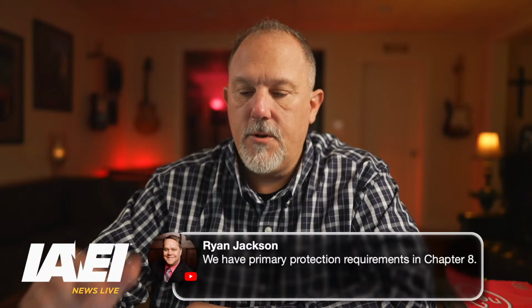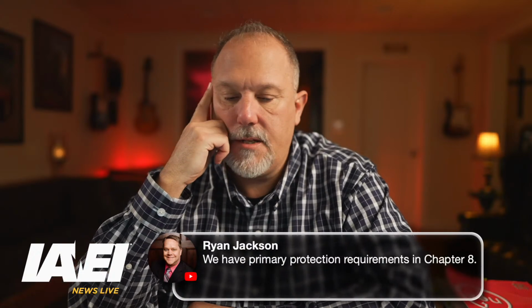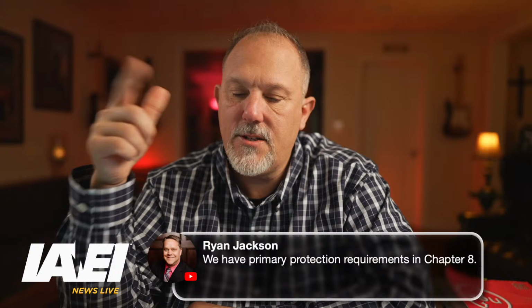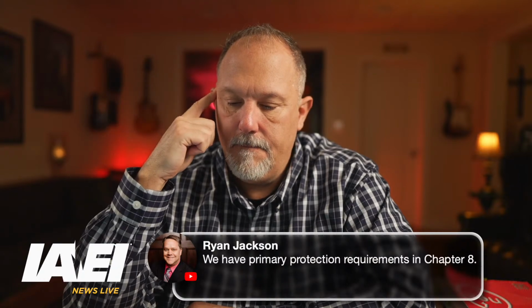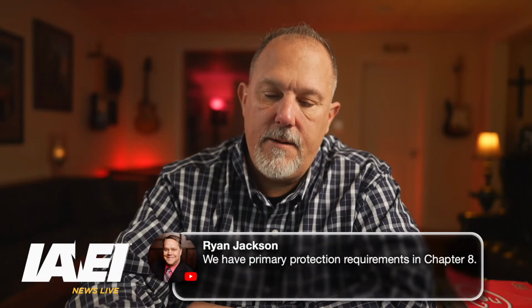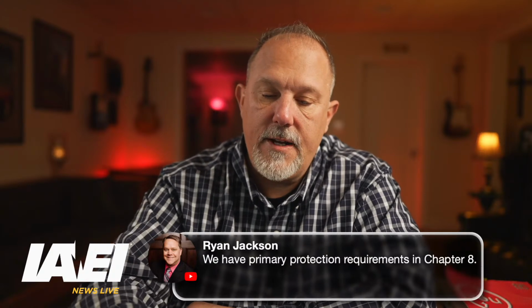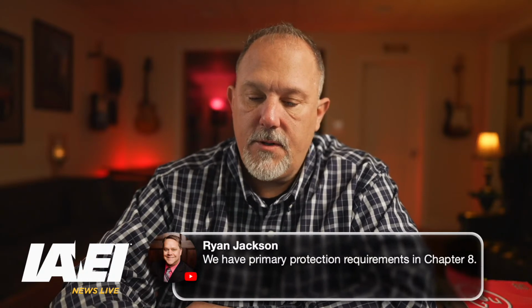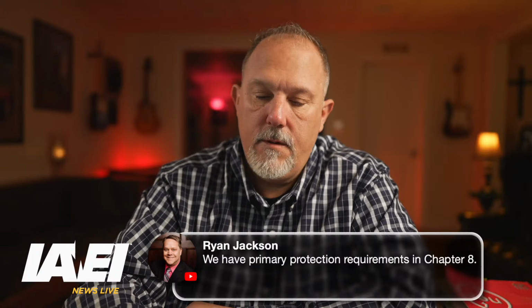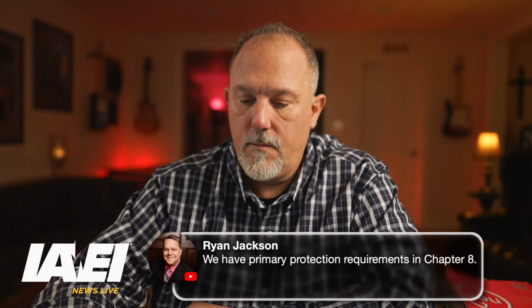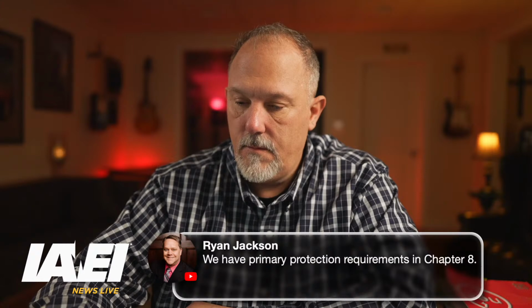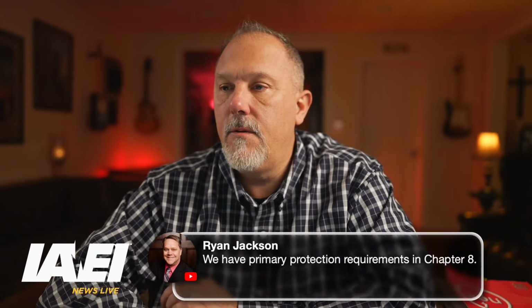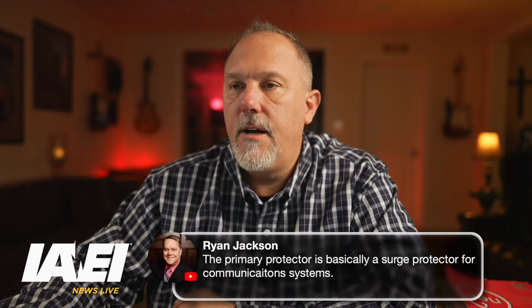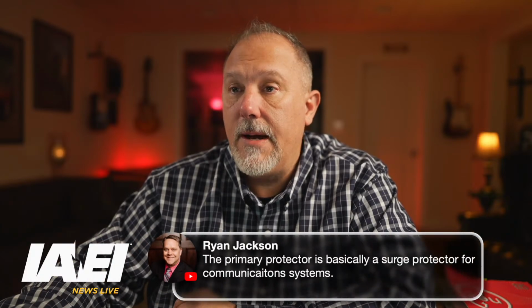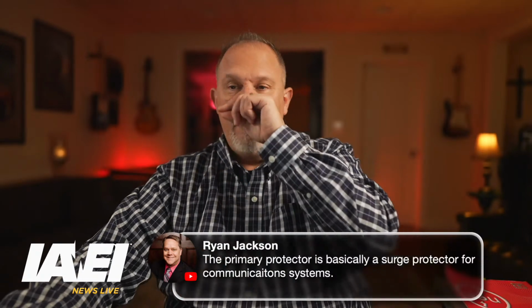A bonding jumper not smaller than number 6 shall be connected between the grounding electrode and power. That's what I was talking about earlier. But that's the only place I have surge that I can find in Chapter 8, Ryan. But I'd love to know. Primary protector is basically surge protector for communication systems. The primary protector. Excellent. Beautiful.